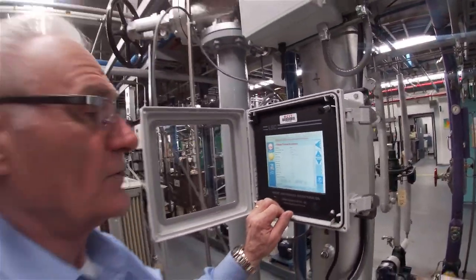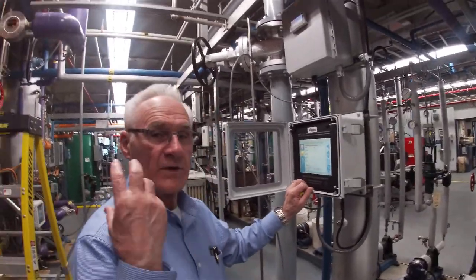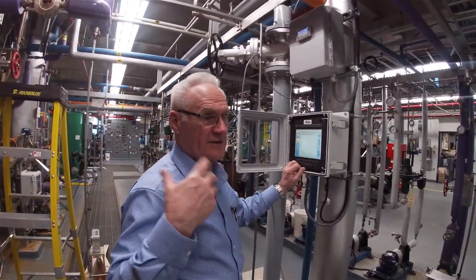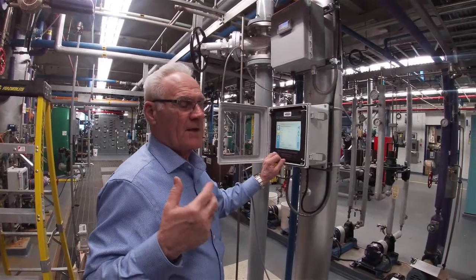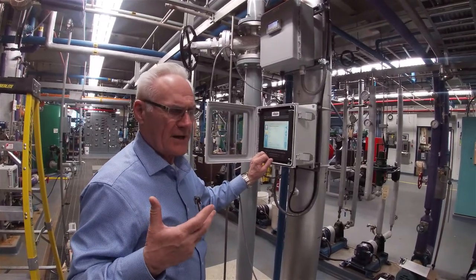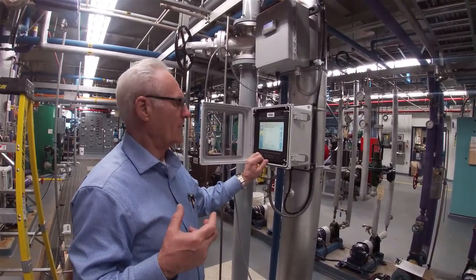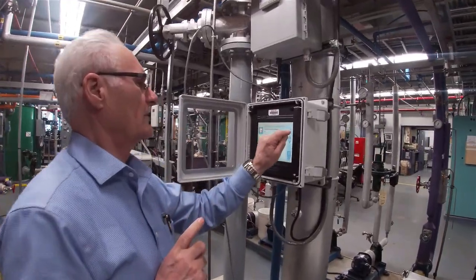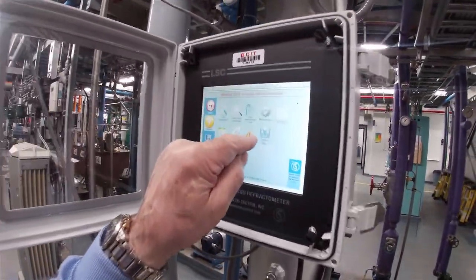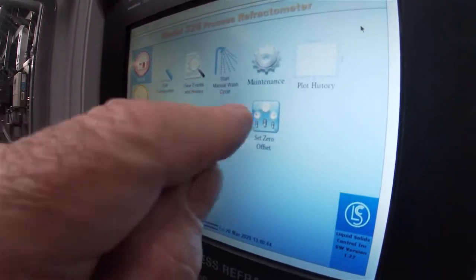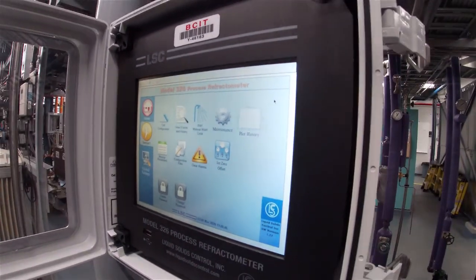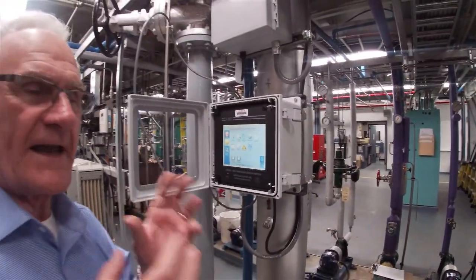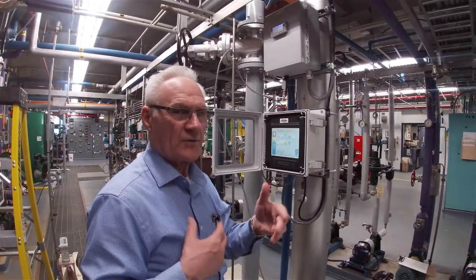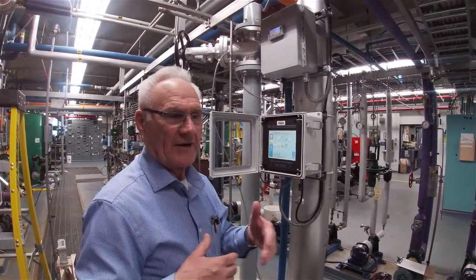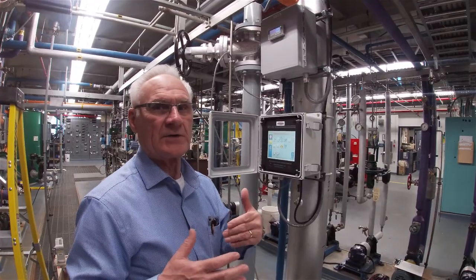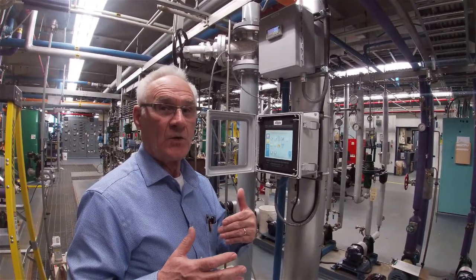Next thing we have to do is to take the head, reinstall it back into the process, so that's just reversing what we did. Then we'll start the plant up, get it running, then we'll take a grab sample, and then what we're going to do is to do something called a zero offset, which is right there. And so we'll touch that button, and then we'll enter in the value of the sample that we took. So we'll have to measure it with a hydrometer and refractometer and a graph to determine exactly what the percent ethylene glycol is. Okay?